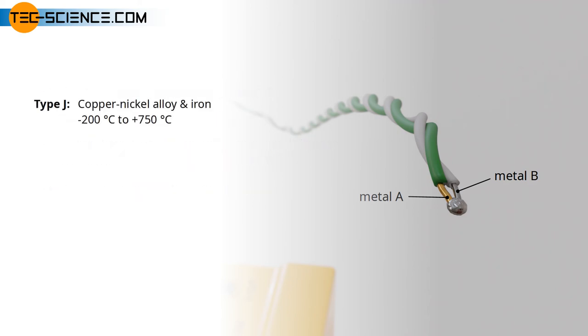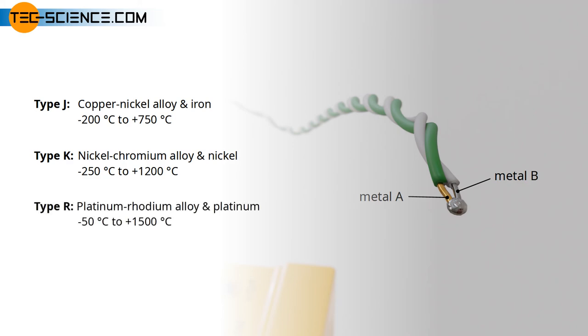Type J: copper nickel alloy and iron. Can be used from approximately minus 200 degrees Celsius to 750 degrees Celsius. Type K: nickel chromium alloy and nickel. Can be used from approximately minus 250 degrees Celsius to 1200 degrees Celsius. Type K is the most common type in private use.